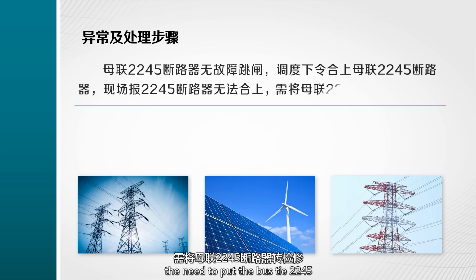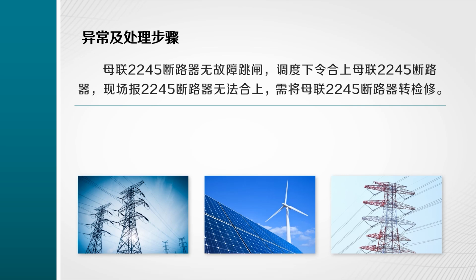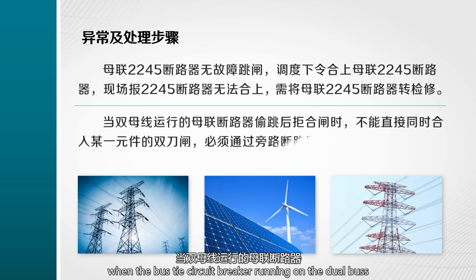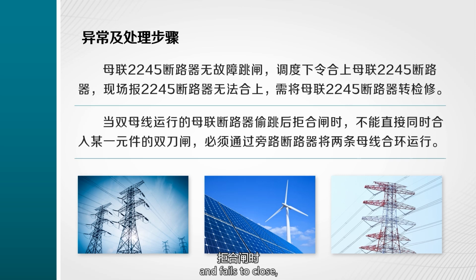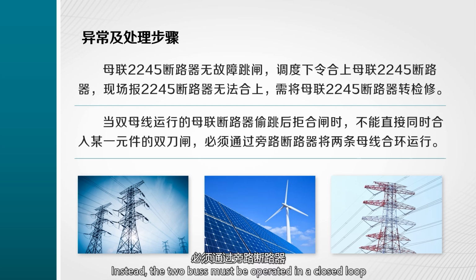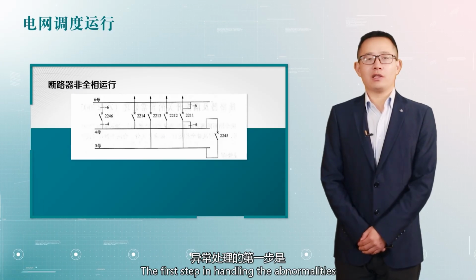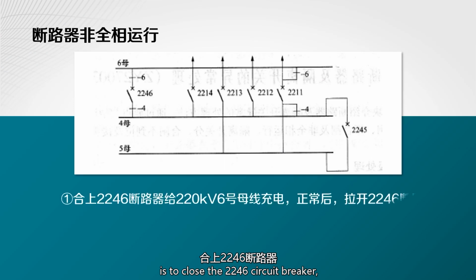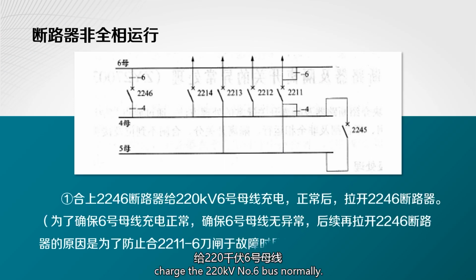Firstly, we should consider the need to put the bus tie 2245 circuit breaker in maintenance mode. Secondly, it is important to note that when the bus tie circuit breaker running on the dual bus accidentally trips and fails to close, it is not possible to directly close the dual knife switch of a certain component at the same time. Instead, the two buses must be operated in a closed loop through a bypass circuit breaker. The first step in handling the abnormalities is to close the 2246 circuit breaker. Charge the 220 kV number 6 bus normally.